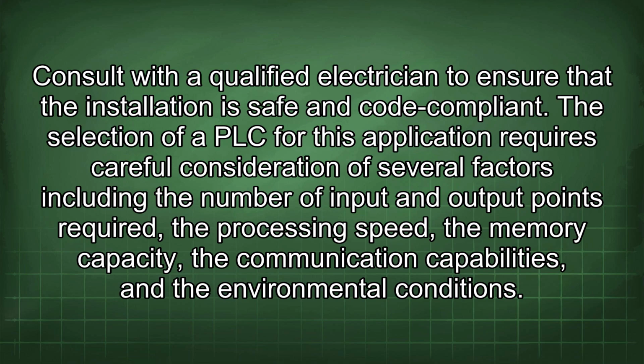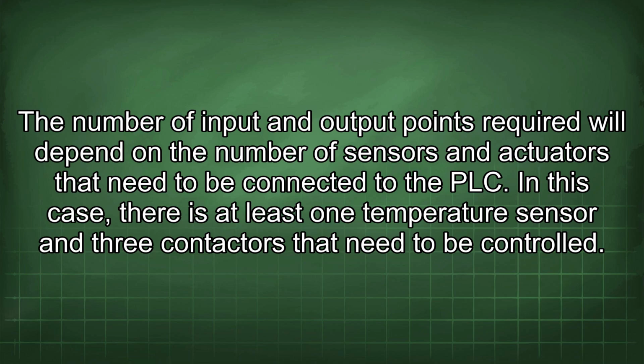The selection of a PLC for this application requires careful consideration of several factors, including the number of input and output points required, the processing speed, the memory capacity, the communication capabilities, and the environmental conditions. The number of input and output points required will depend on the number of sensors and actuators that need to be connected to the PLC. In this case, there is at least one temperature sensor and 3 contactors that need to be controlled.